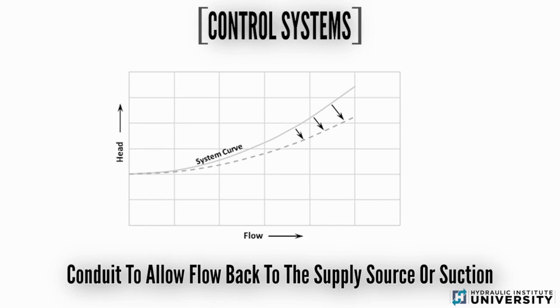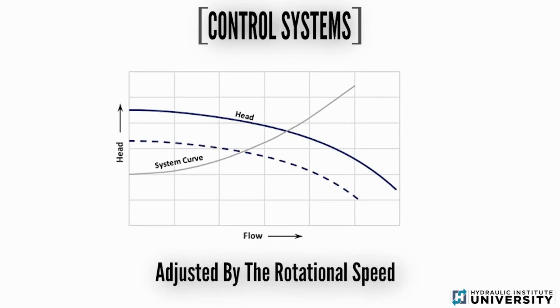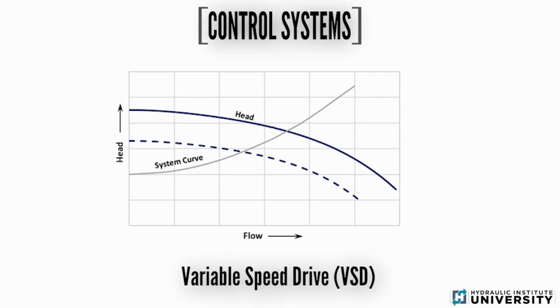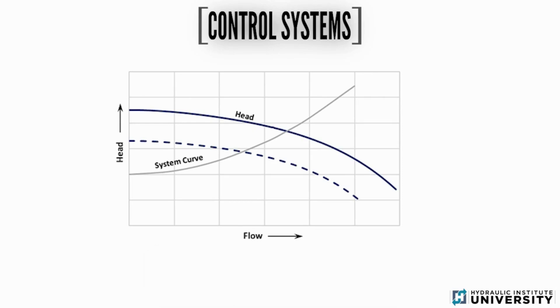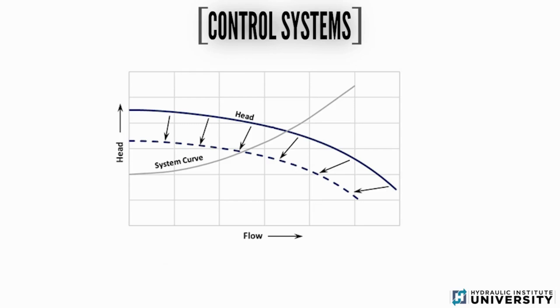On the other hand, the pump curve can be controlled by varying the pump speed. Varying the rotational speed of the pump is achieved through a variable speed drive (VSD) or variable frequency drive (VFD), which alters the pump's performance characteristics. Note that as speed is reduced, the pump performance curve shifts downward.